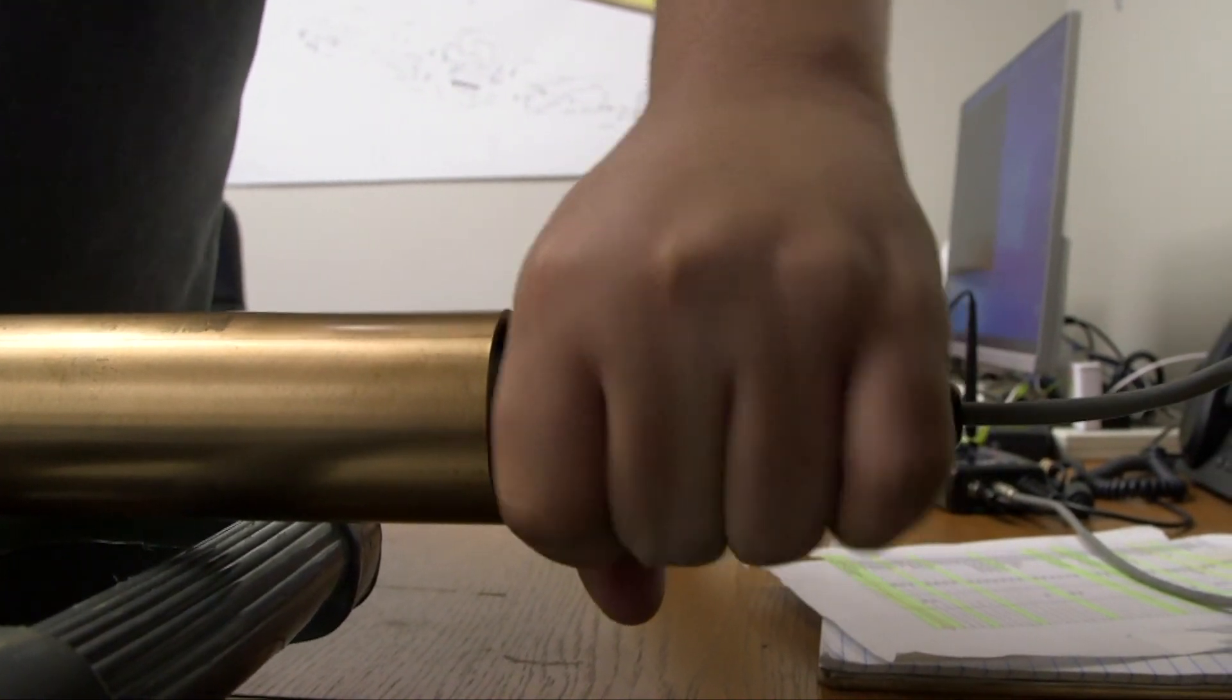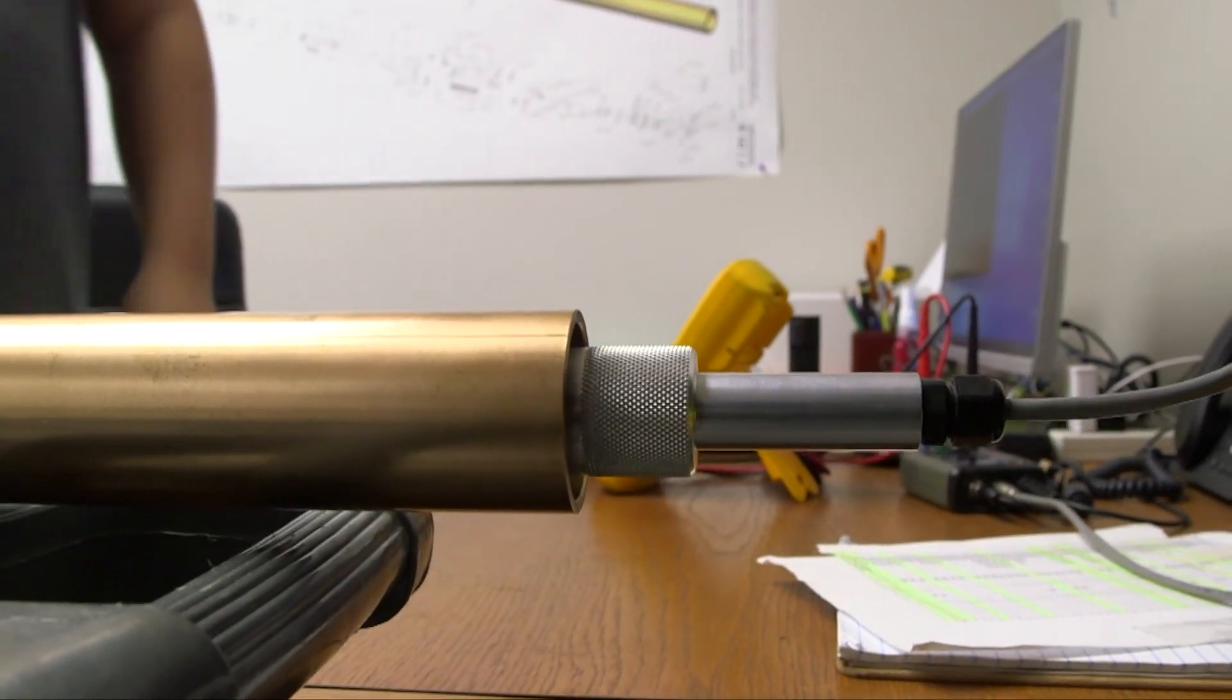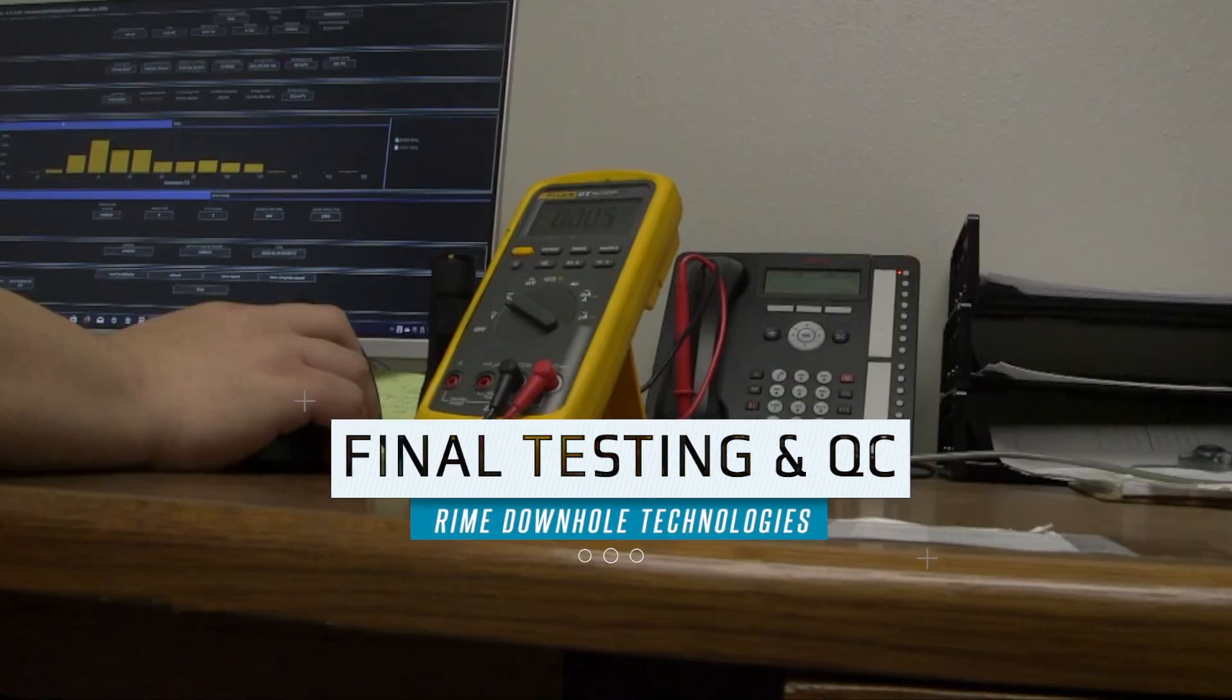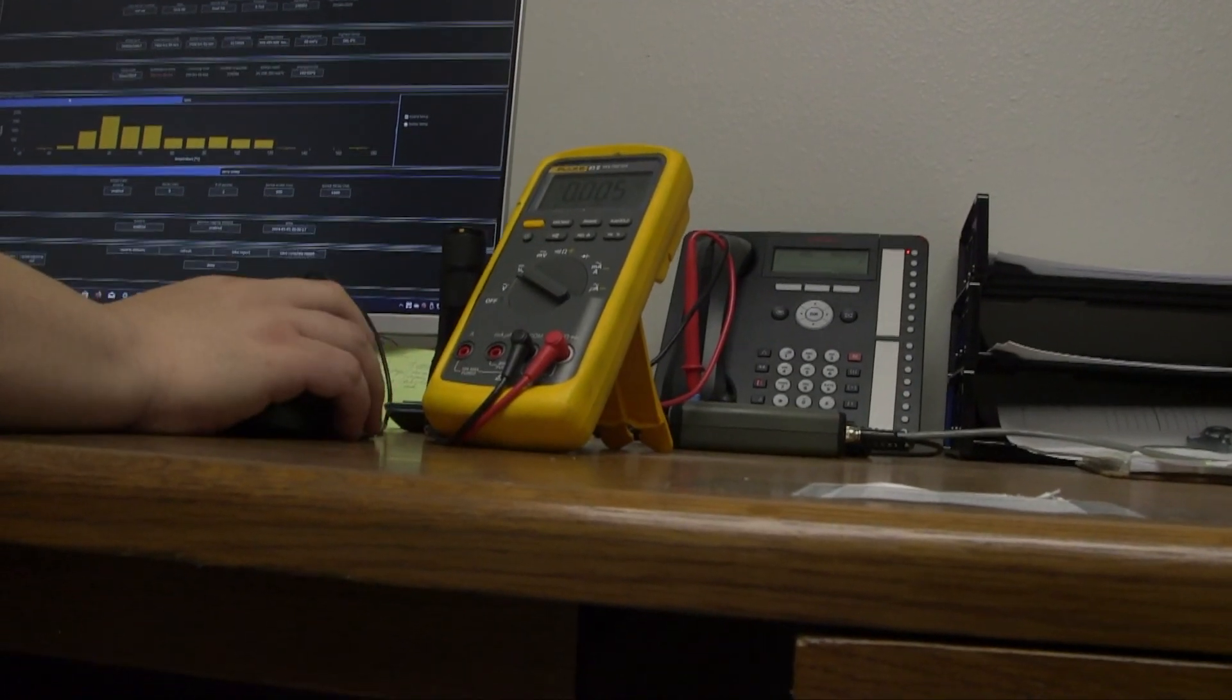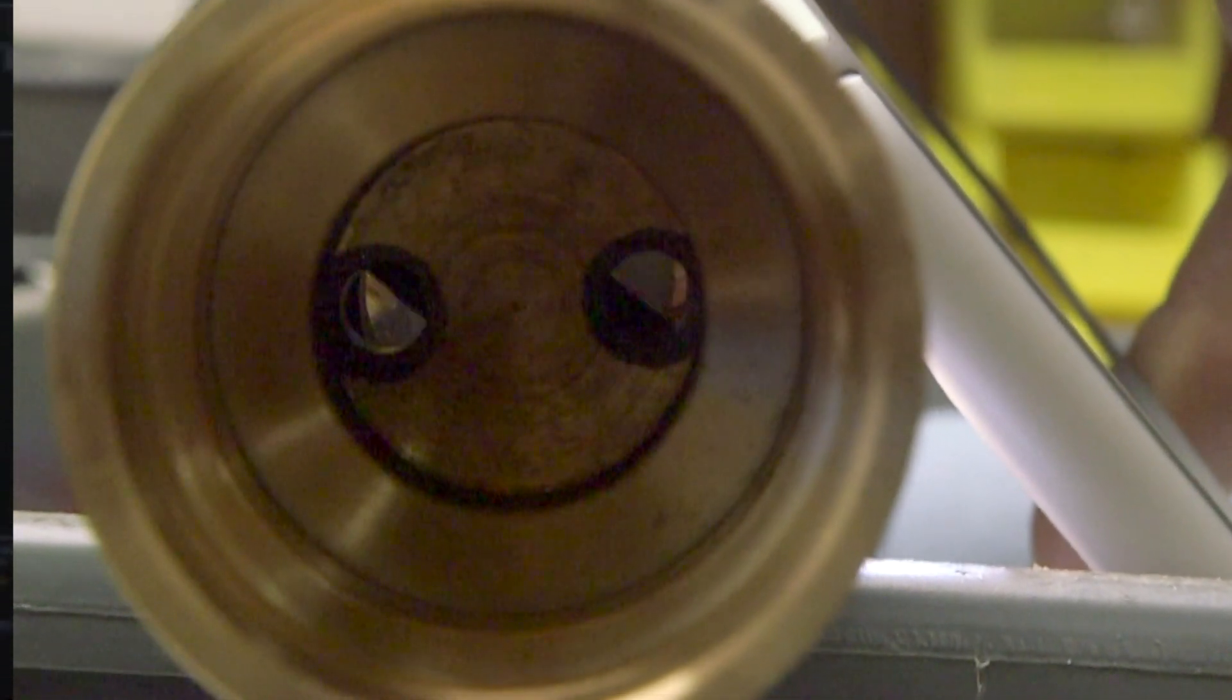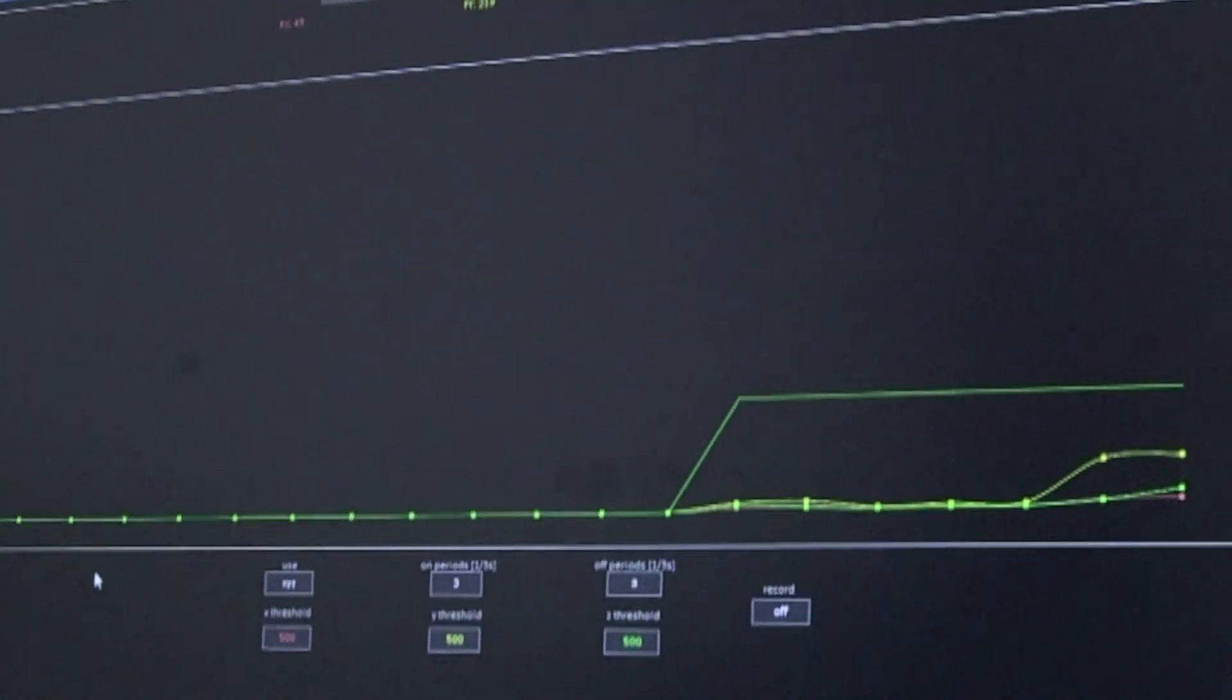The Pulsar is connected to our Pulsar Interface Program software through our Pulsar Interface box. The Pulsar is pulsed continuously using our software to verify that the energy consumed is within acceptable limits and that the valve's full range of motion is checked visually and using our software.